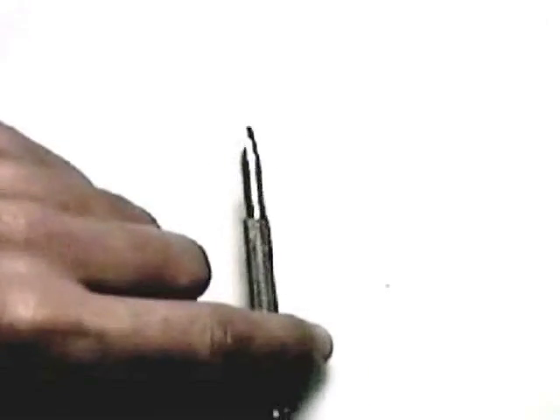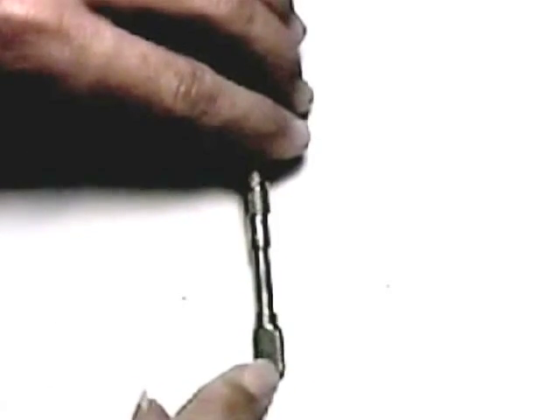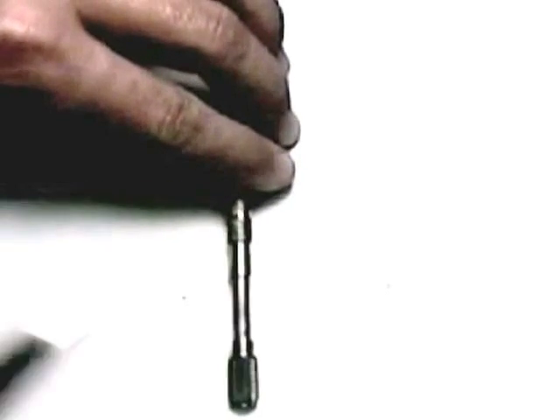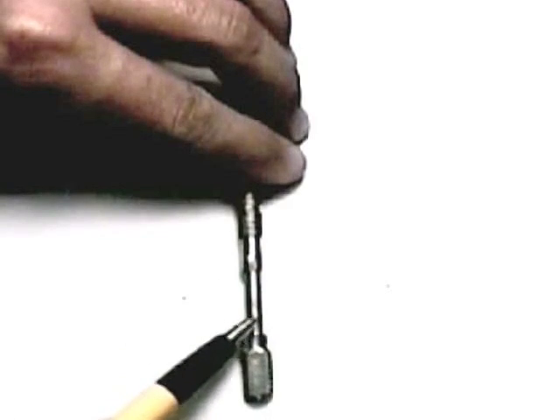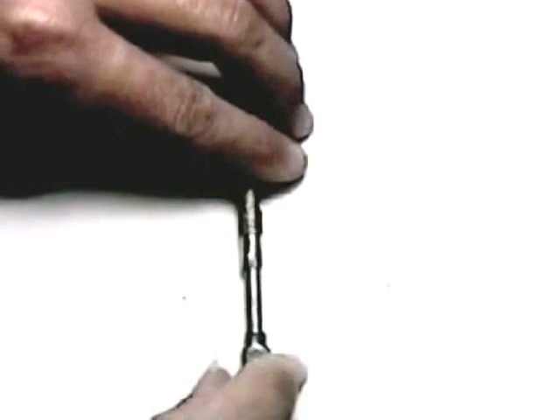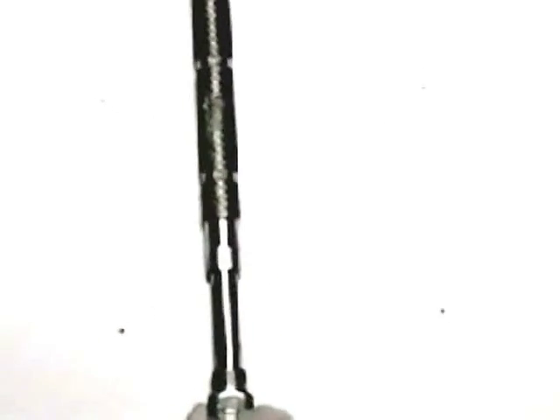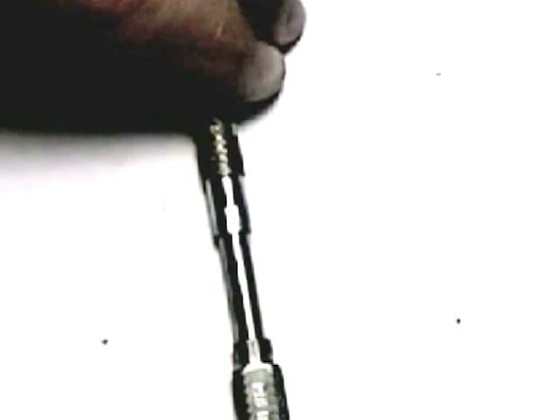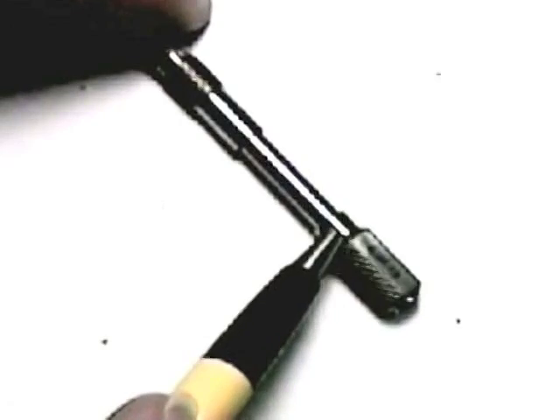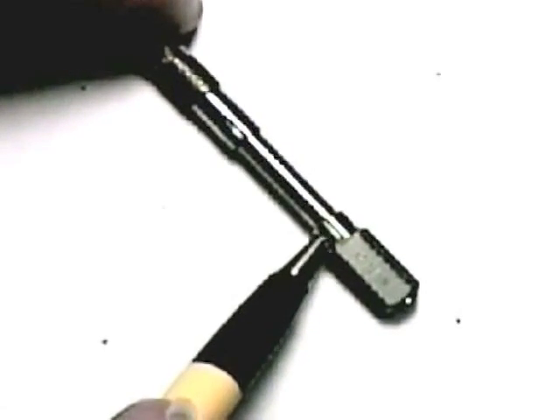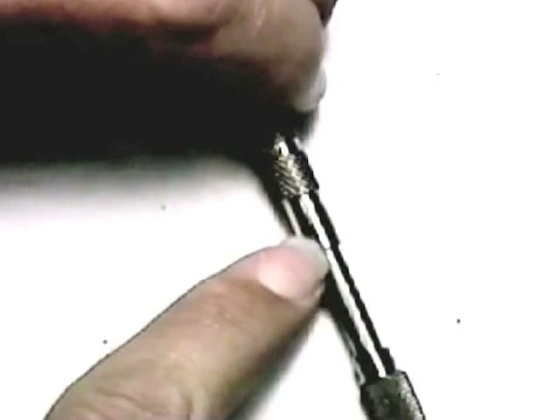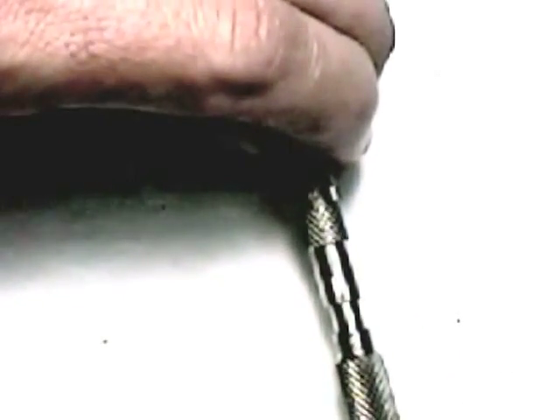For example, when setting this blade to full retraction, you can see two small flat ridges right here and here. And I'm going to try and focus in here to make it easier to see this. You can kind of see these flat ridges here. When these two ridges are lined up, it means the knife is in the retracted position. However, you can also see, hopefully, well, not very well, but there are numbers right here which represent the pre-calibration setting. For example, this number reads 4.5, which means when you line up that number to that flat ridge, the blade is extending 4.5 millimeters beyond the foot plate, as you can see here.